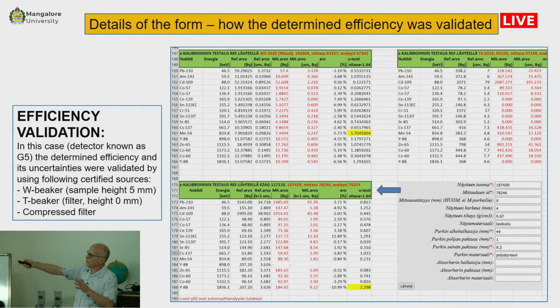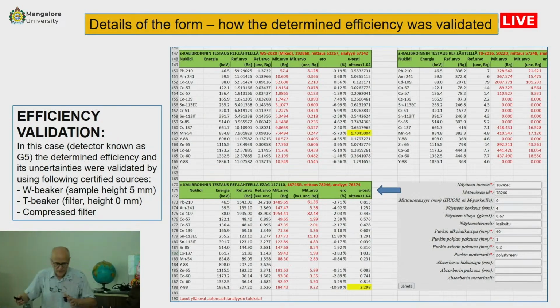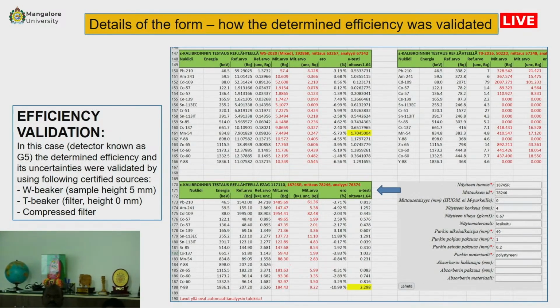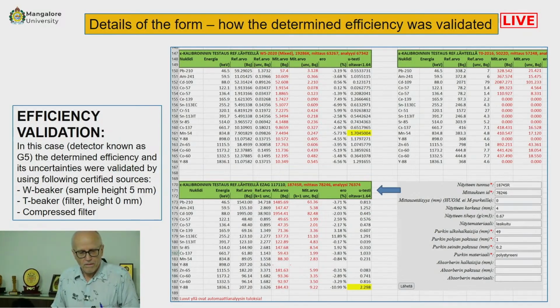But remember that this is not our basic efficiency calibration. This is only for checking that our so-called T20 calibration is correct, because this is our starting point, this T20 calibration. Just to check. So originally, the first time when you do it, you use high strength sources.